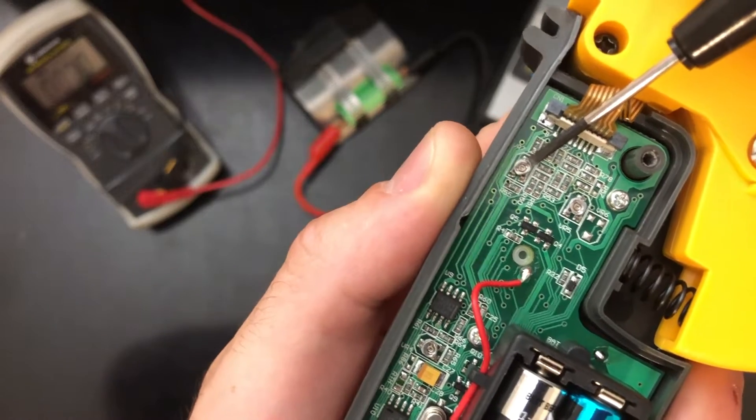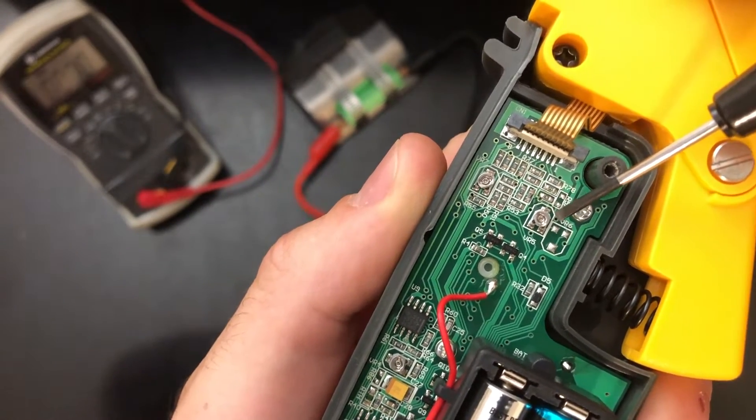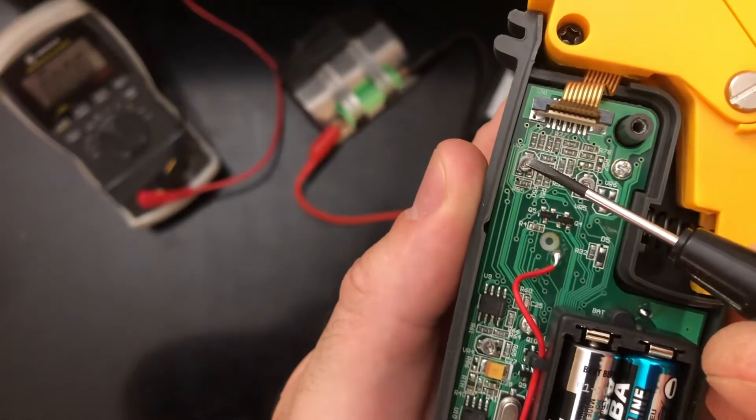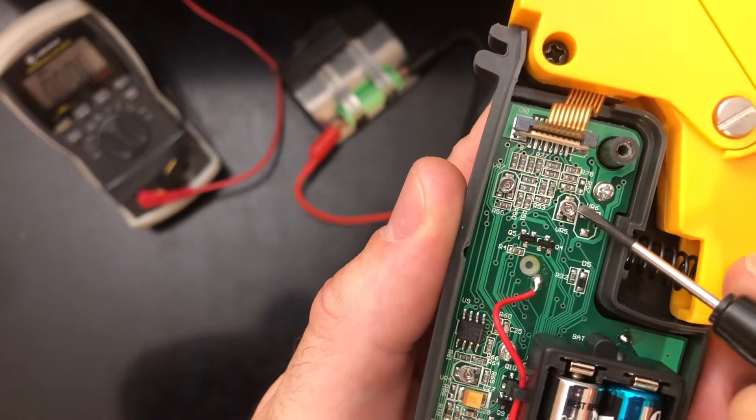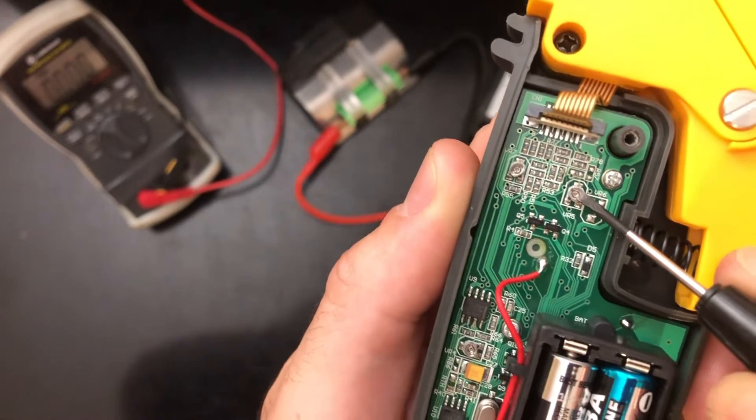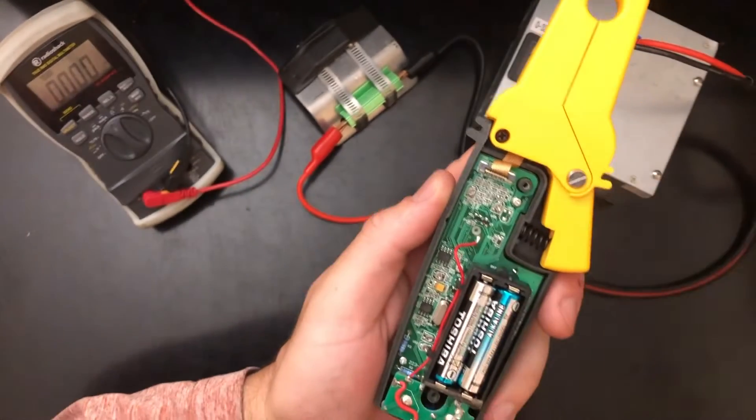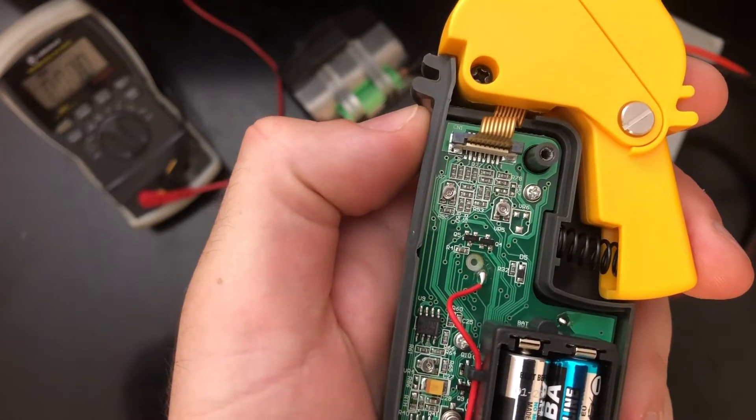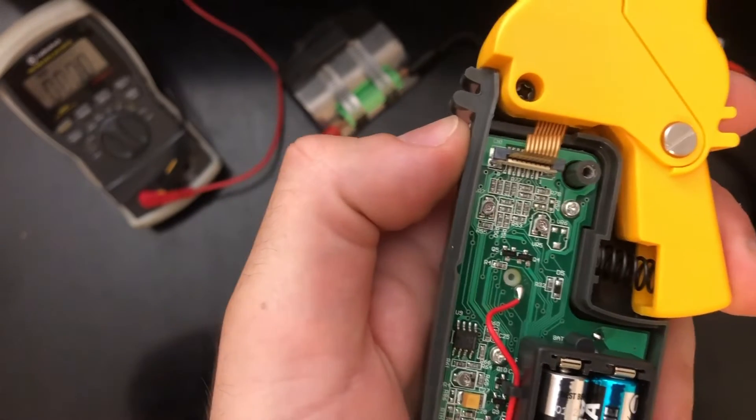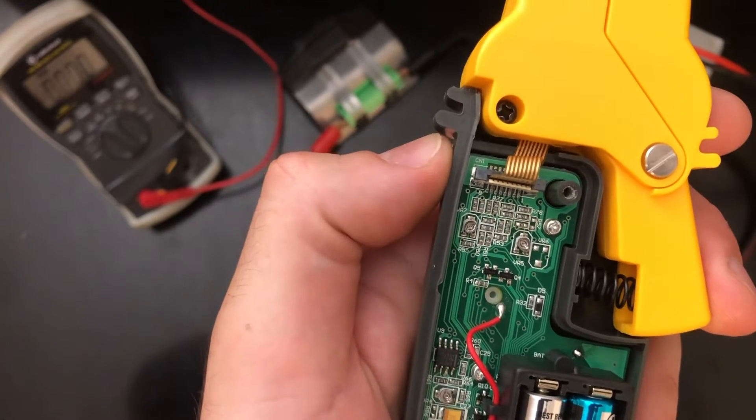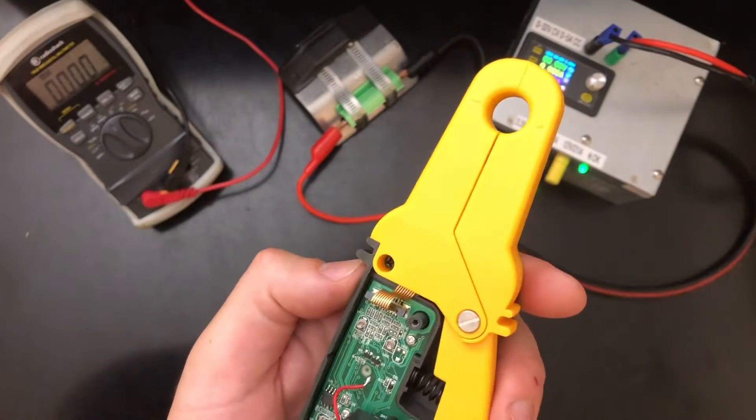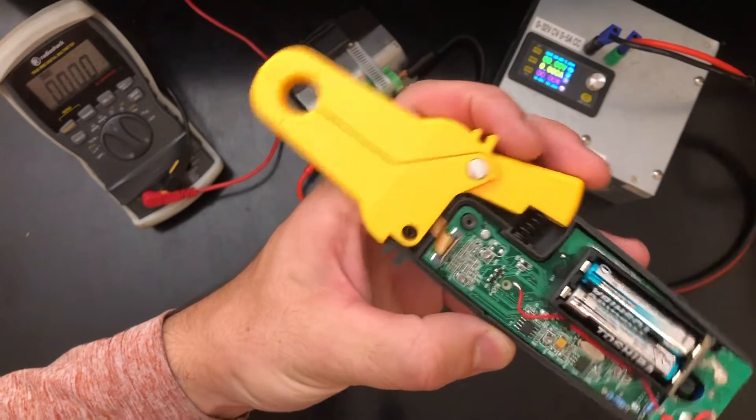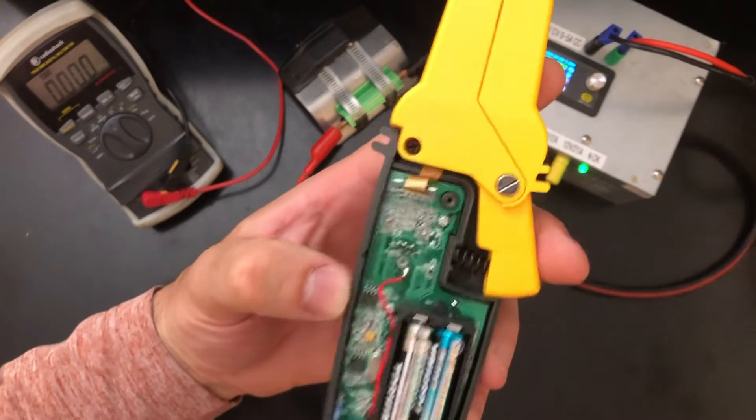This one on the left side, this is your zero. This one on the right side, this is what you trim for some current above zero. So what I'll be doing is setting this initially to zero with nothing flowing through it, and then I'll put on the five amp dummy load again, and I'll turn this pot until I see five amps going through it. This is about a 10 amp capable DC clamp meter, so five amps seems like a good place to set that calibration at, but you could use it at two and a half amps or wherever the range is that you're most commonly measuring if you really wanted to dial in for ultimate precision. At the end of the day, this is a Hall effect sensor. It's going to have a little bit of variance to it no matter what you do. If you want a really precise measurement of DC, you're better off using a shunt. But in this case, I'm going to set it to five amps, so it's about correct for the middle of the range.